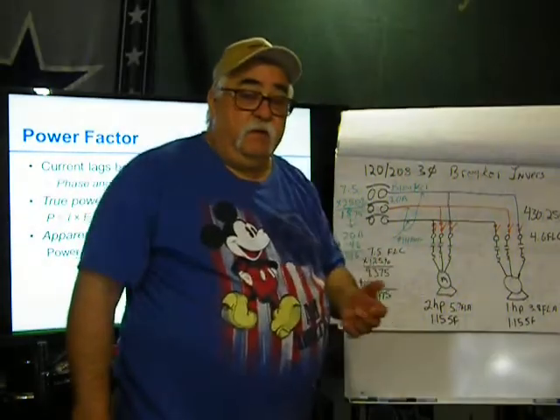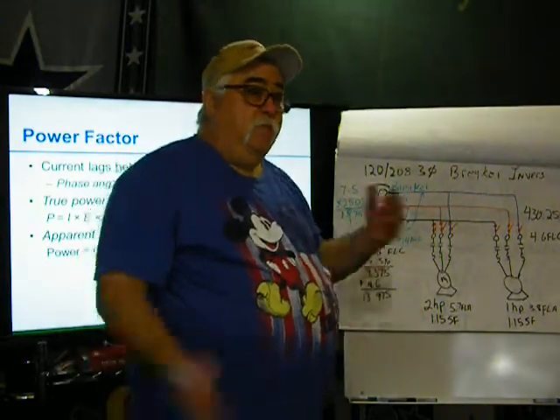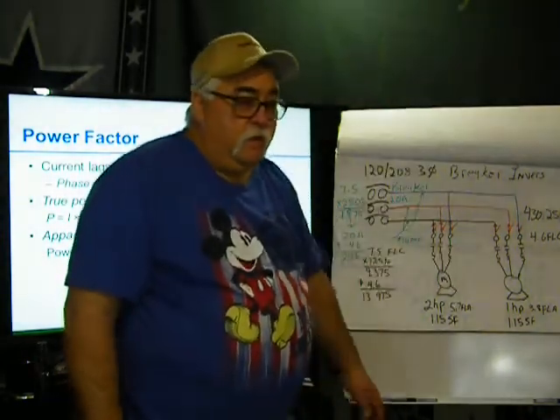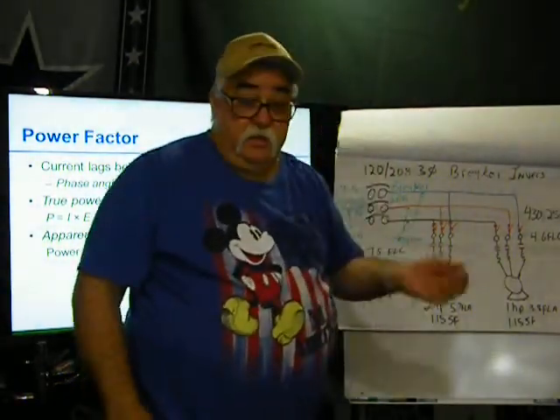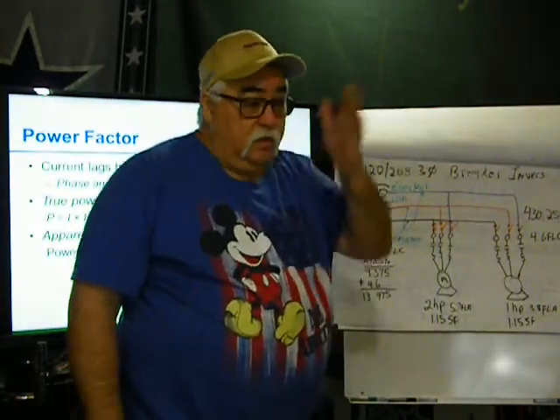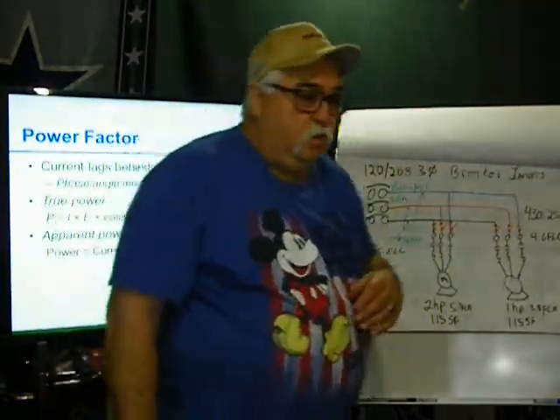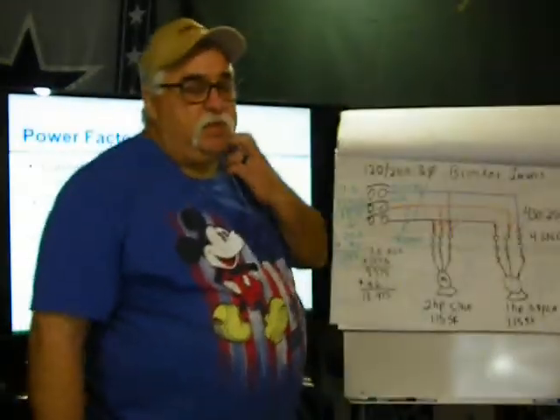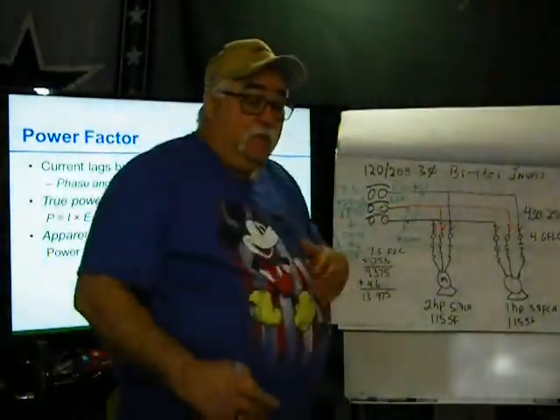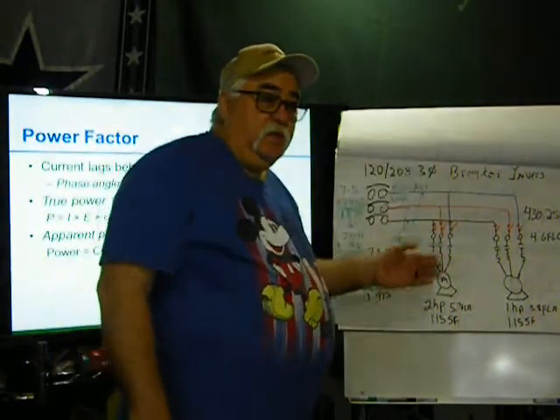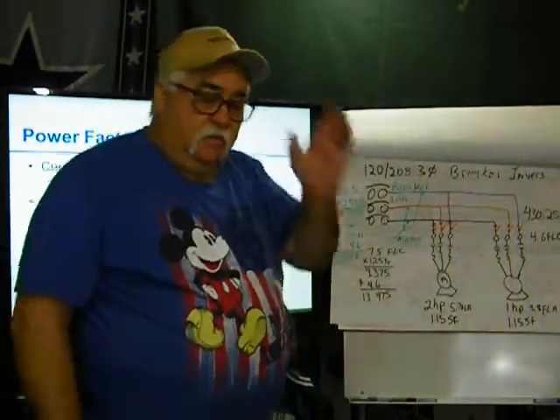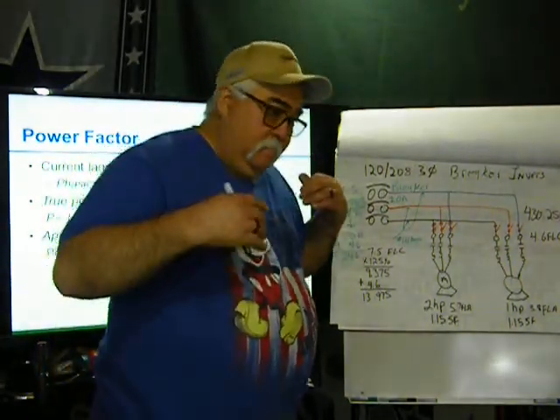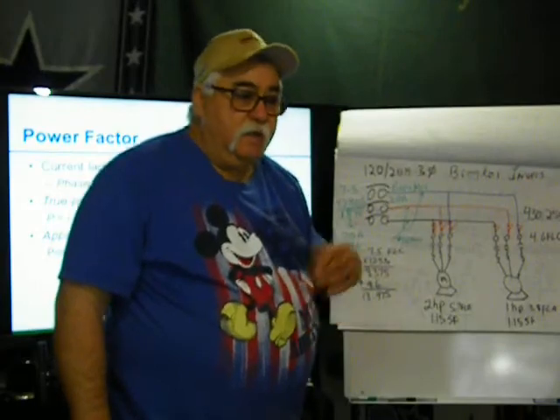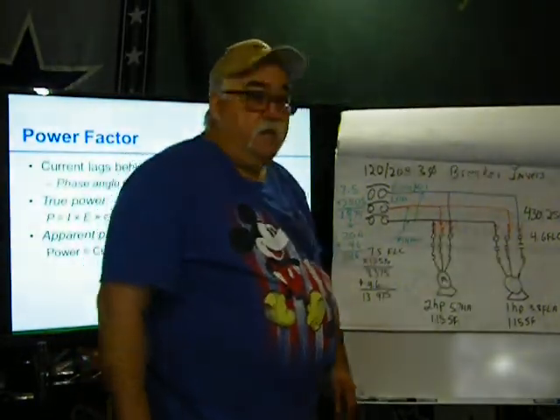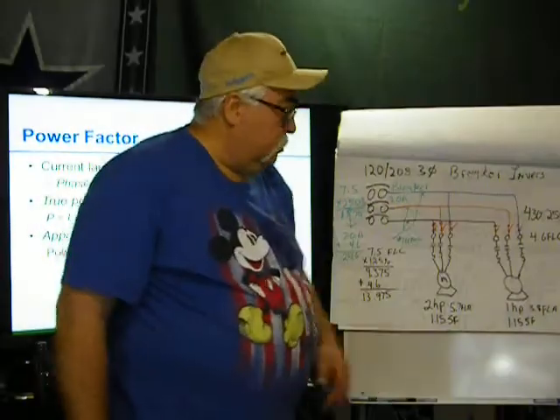14 gauge at 75 degrees C, it can handle. Before, we talked about, well, we don't know what our terminations are. Are they 60 or 75? A lot of people have a tendency to look at that 60. For most parts in today's world, we can use 75 degrees C. Always remember, at 100 amps or less we go to that 60 degrees C. More than 100 amps, we go to the 75 degree. But in today's world, out there on the outside, 75 degrees C on everything is okay, unless you already know it's going to be 60 degree.